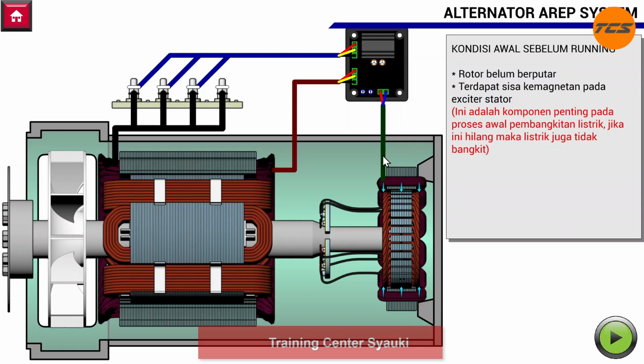Before the generator starts, the rotor is not rotating yet. At this stage, there is residual magnetism present in the exciter stator. In some generator designs, small permanent magnets are installed in the exciter stator to ensure this residual magnetism. However, in the Leroy Somer generator used in Weichai gensets, no permanent magnets are installed. Therefore, residual magnetism becomes a very important factor in the initial voltage build-up. If residual magnetism is lost, the generator will not be able to generate electricity.